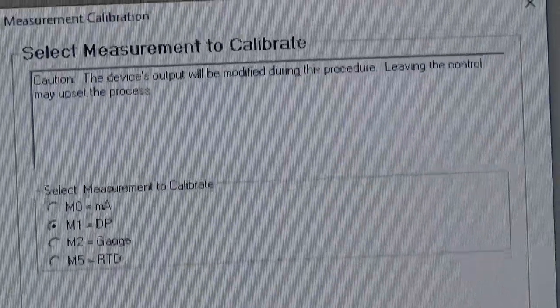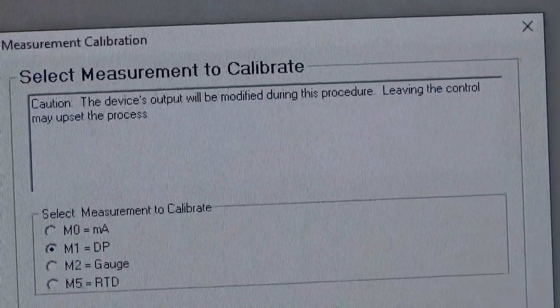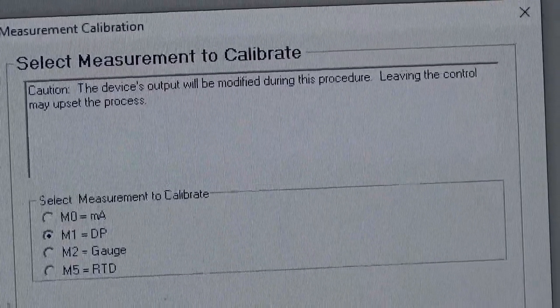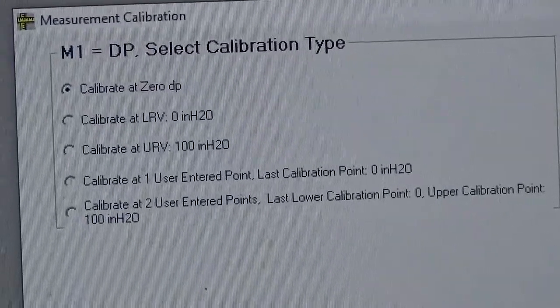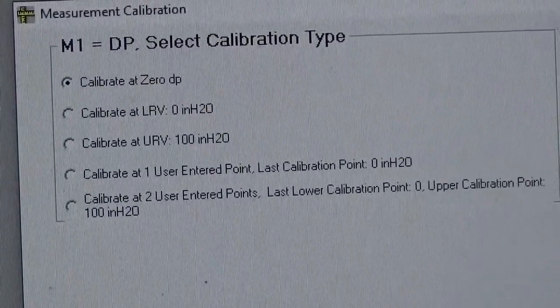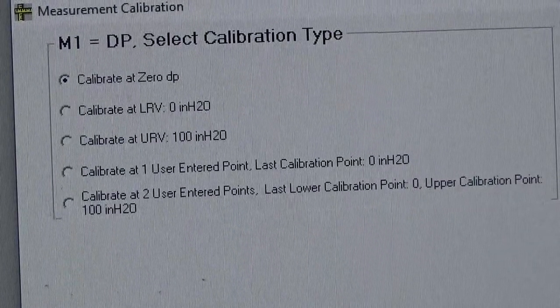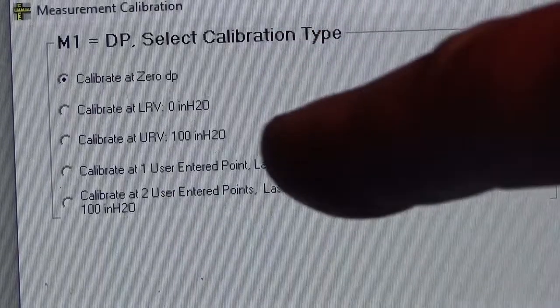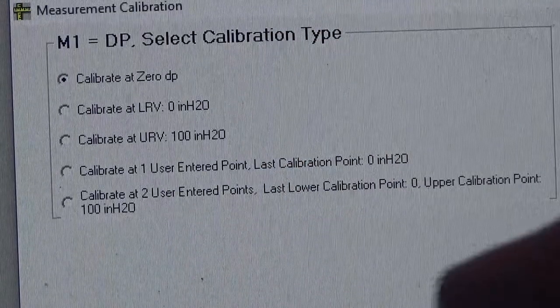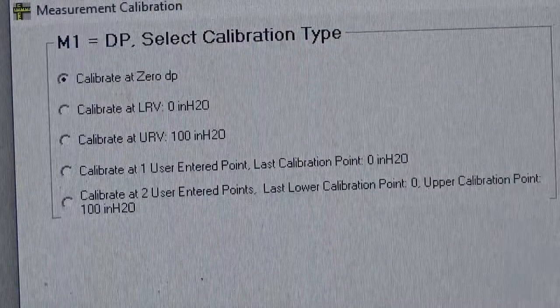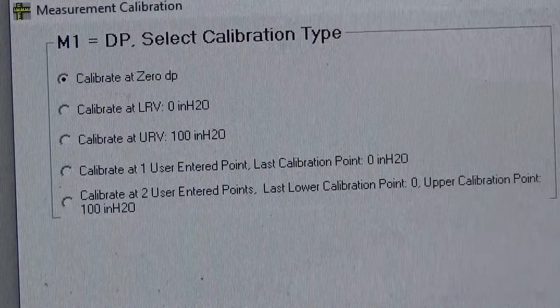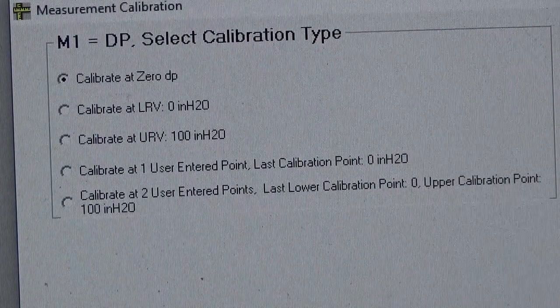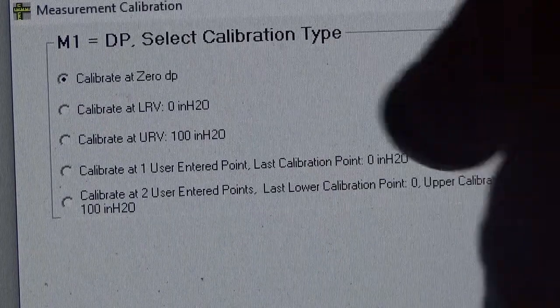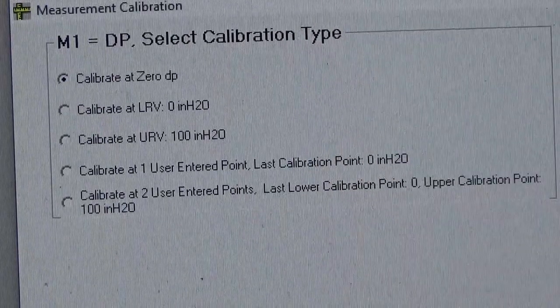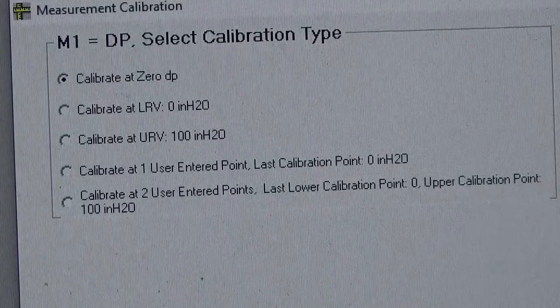And we're going to wait for the next calibration screen to appear, which is going to ask us which points we want to calibrate. So we can just do a 0 cal, or a lower range or upper range, or we can calibrate one user entered point or two user entered points. In this procedure, I'm going to elect to do the lower and the upper range values, 0 and 100.